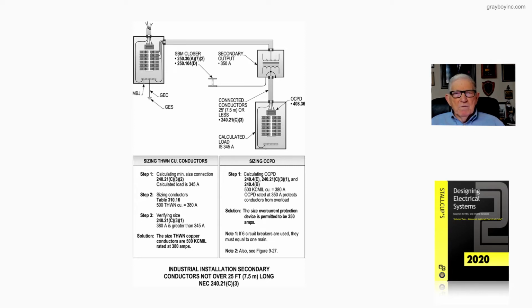But if you tap over 10 foot up to 25 foot, as this section allows you to do, this overcurrent device that you see in the panel board in the illustration has to protect the conductors plus the transformer output. So looking at the illustration and looking at sizing the THWN copper conductors that we're going to select, notice that we apply what's required in 240.21(C)(3) item 2, and the calculated load is 345. Already calculated now. It's already calculated for us.